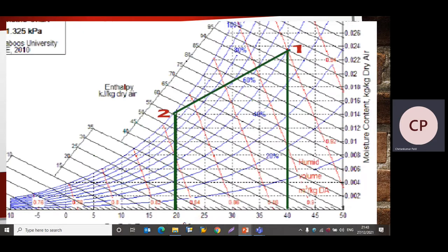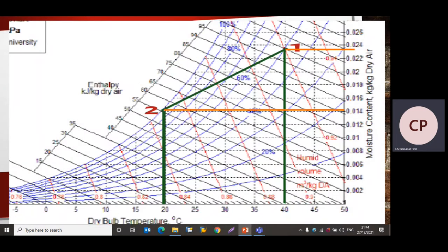Now we will move to Point 1. The condition for Point 1 is dry-bulb temperature 40°C and relative humidity 50%. We draw a vertical green line at 40°C, and the relative humidity lines in percent indicate the curved lines on the chart. The intersection of the 40°C vertical line and the 50% relative humidity line gives us Point 1.